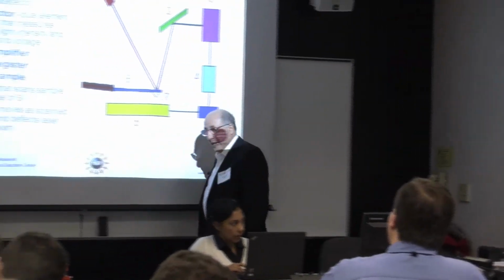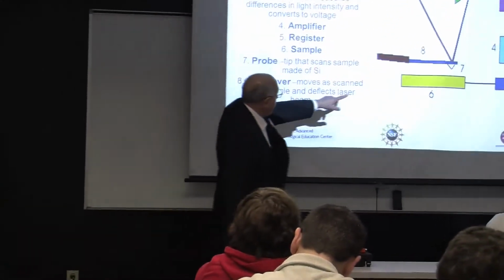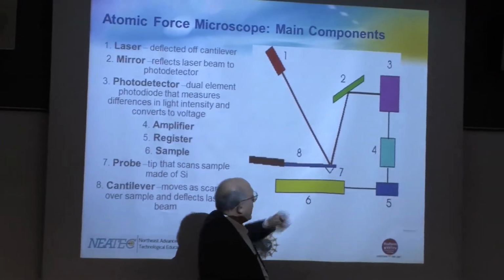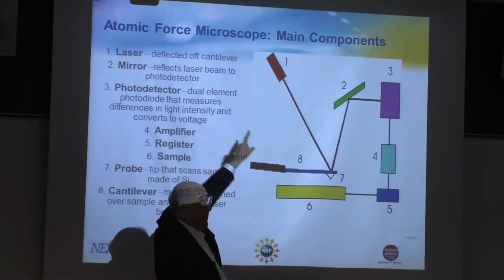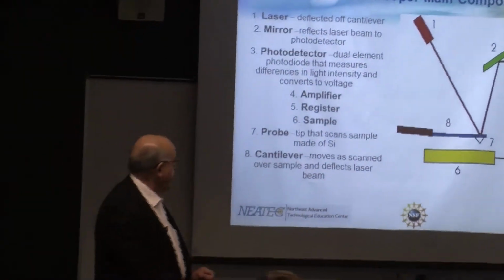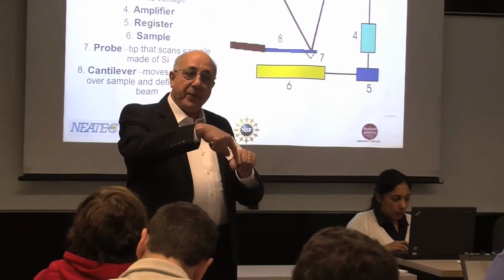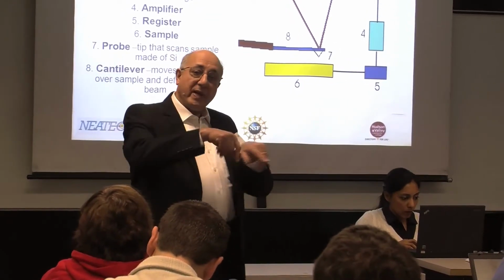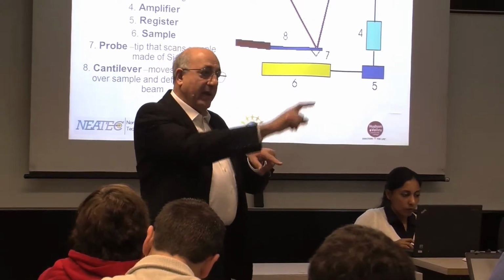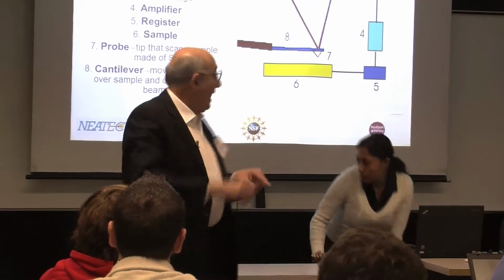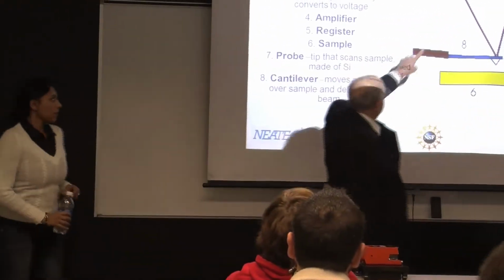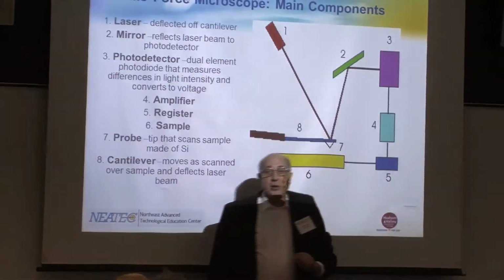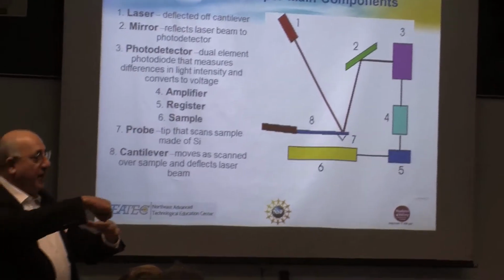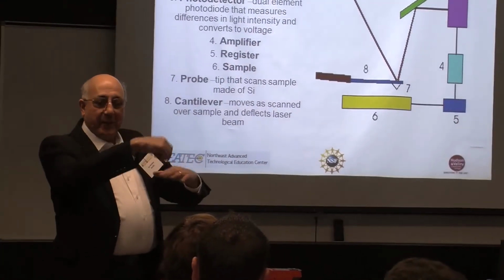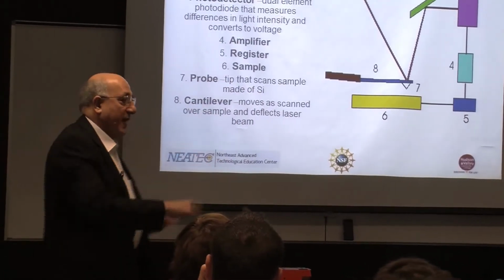Let's look at all the parts of the AFM. Here you have the sample. This is the cantilever. Here you have the tip. And we have a laser beam, normally a diode laser, pointing continuously to the tip of the cantilever. You can see that because there is a light on the cantilever, and as you move the cantilever, it will move up and down. Then the light produced by the laser will impinge on a mirror, and because the tip is moving up and down, the light will also move up and down.